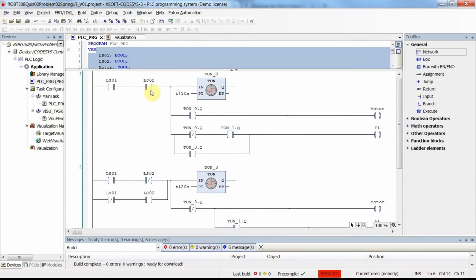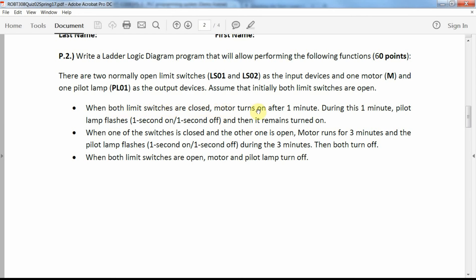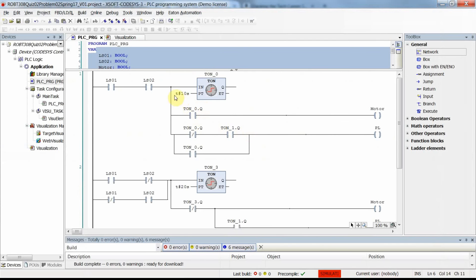When both limit switches are closed, we want the motor to turn on after one minute — but here I've used 10 seconds so you don't have to wait. We can do this using an on-delay timer with a preset time of 10 seconds. The timer receives input from LS01 and LS02 in series, and after 10 seconds the done output of the on-delay timer becomes true, turning the motor on.